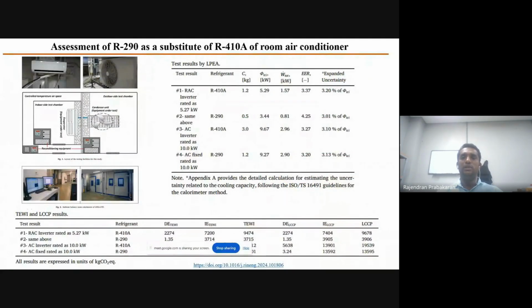And this study also introduced the same R290 refrigerant as a replacement for R410A in slightly bigger systems, up to 10 kilowatt capacity. This system also showed good performance at high capacities as compared to the 5.2 kilowatt system. We can see the test results in the upper table. It also had 14 to 34% reduced LCCP and TEWI. So all these studies suggested that we can use R290 in room air conditioning applications successfully.